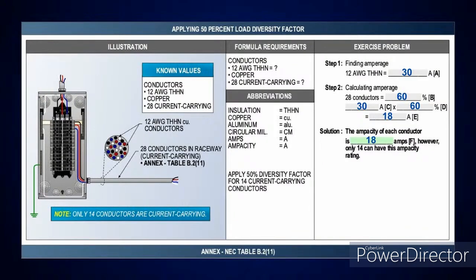Now, this is the one where we started talking about it having a 50% diversity factor. Basically, in this case, I've got 28 conductors. If I've got 28 conductors with a 50% diversity, that means 14 of them will be current carrying. You'll see the note there. The same calculation applies. You just go look at table B.2(11), and for 28 conductors it tells you to put a 60% derating factor on that. Nothing changed. I've still got 30 amps for the number 12 conductor. I just put a 60% derating factor, and that gave me 18 amps for each conductor because I have a diversity of 50% here.